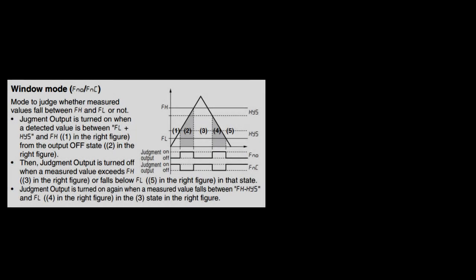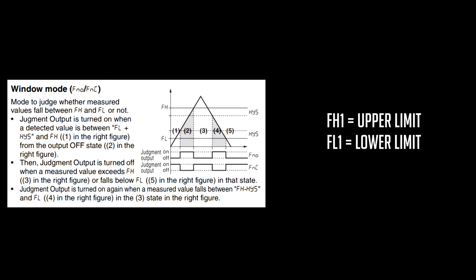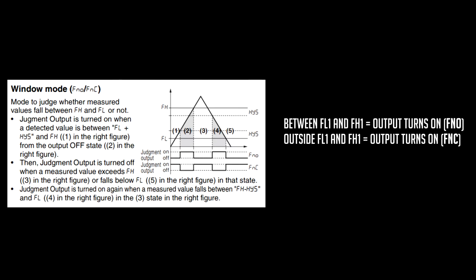The other discrete output detection mode that we have is window mode. In this detection mode, you need to set an FH, or upper limit, and an FL, or lower limit. Once your upper and your lower limit are defined, if your window normally open, your output will turn on in between this lower and upper limit. In window normally closed, your output will turn on outside of your lower and upper limit.